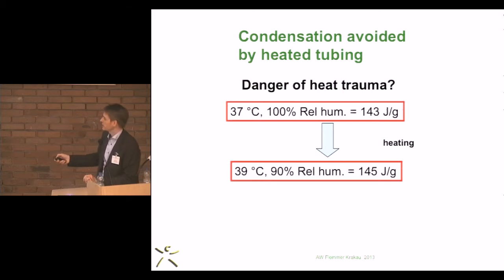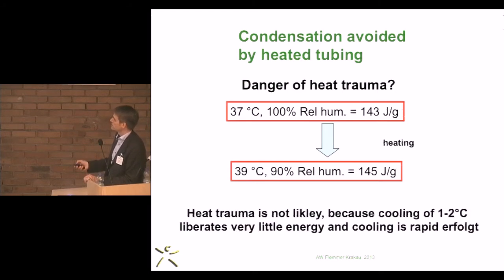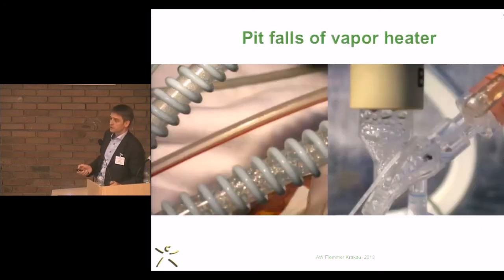the relative humidity, as I've shown you before, drops to actually 90%. And the energy you put in there increases very little. So actually the risk of heat trauma is quite little, especially because on the way down the endotracheal tube, the gas will be cooled down to 37 degrees again, and that has been measured before. So the major risk of inappropriate gas conditioning during invasive ventilation and also during non-invasive ventilation is rainout.